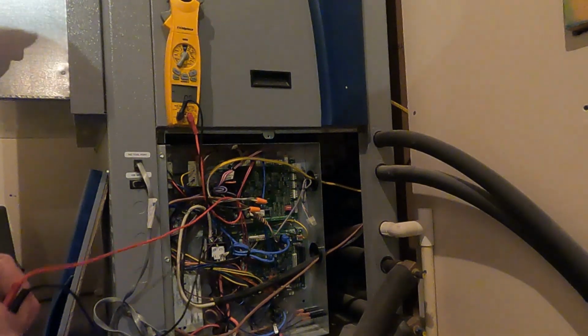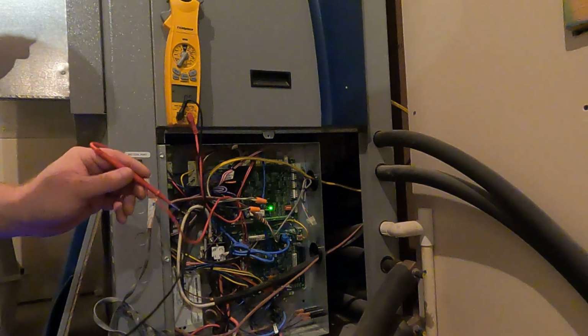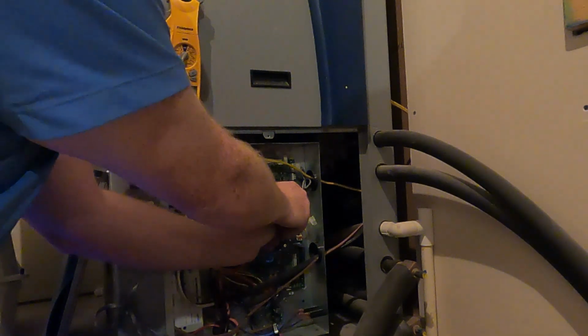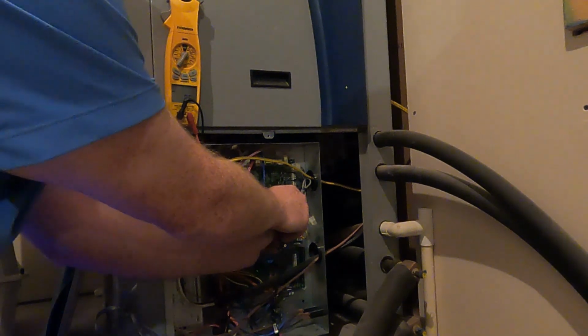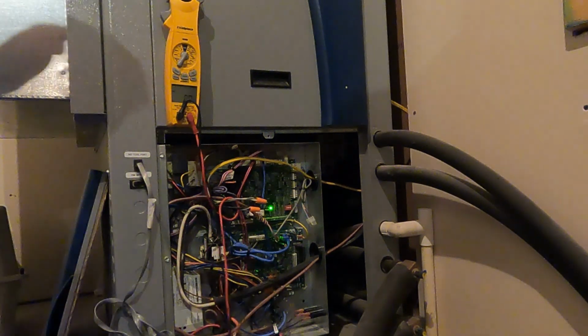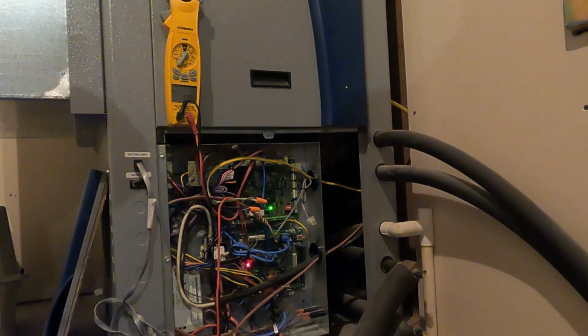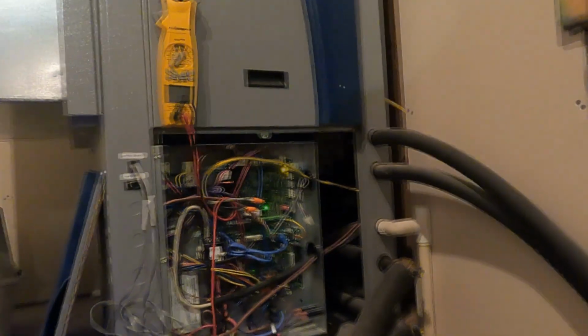Alright, next we're going to go ahead and check the voltage for this thermostat. So I'm going to go ahead and check common to R. And I've got 28.8 volts on my meter here. So the thermostat's getting power, it's just not communicating. So it could be something internal with the thermostat. I'm going to go ahead and reset power to the thermostat, see if anything clears it up that way. Maybe it's just something in the firmware.